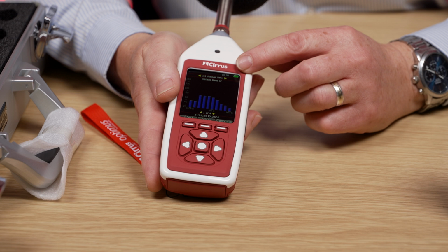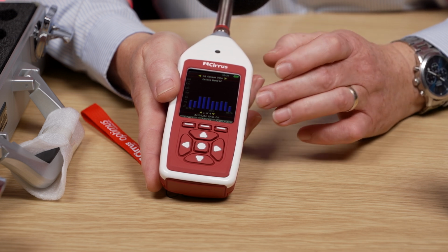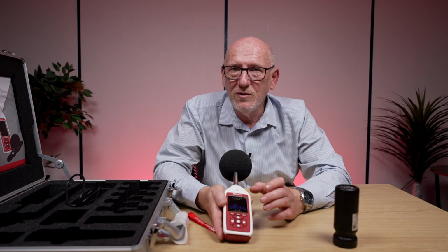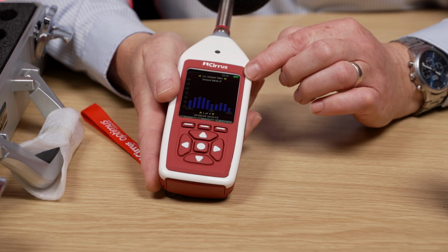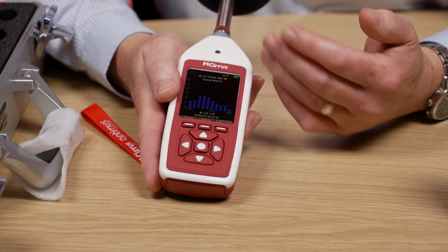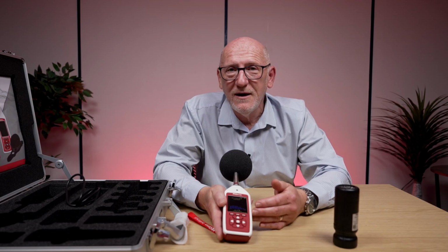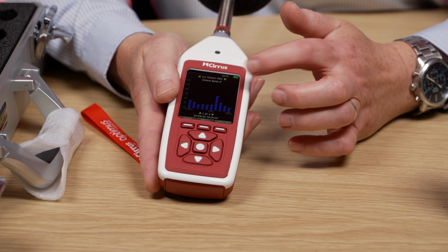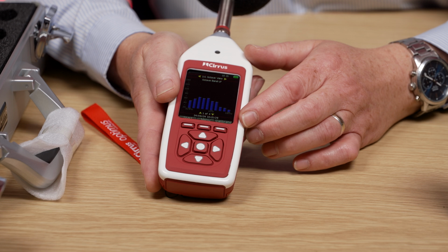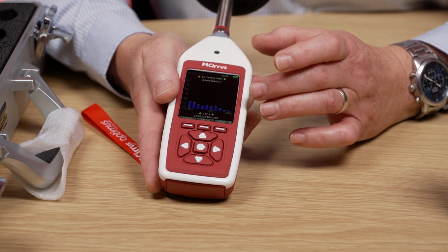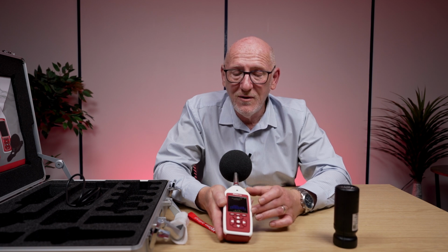This one's the octave band screen. So we've split the frequency components of the noise into 10 individual frequency bands, going from low frequencies on the left to higher frequencies on the right. And as you can see, as I'm talking, you'll see the different frequencies of the noise. Again, if I whistle, you can tell that I like whistling. You can see where that whistle comes in. The frequency was just about 2 kilohertz, something like that. So that's showing you the frequency levels in the noise while we're speaking.